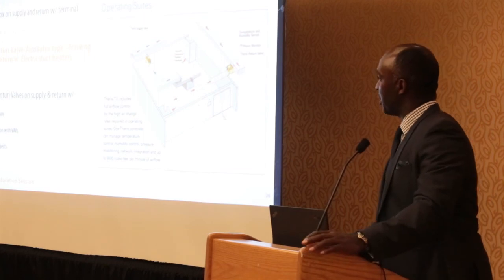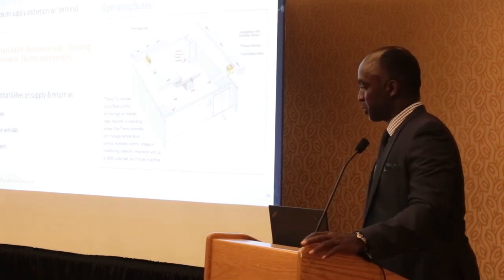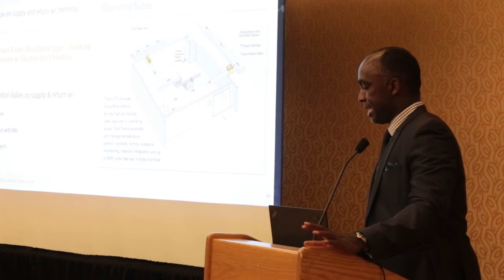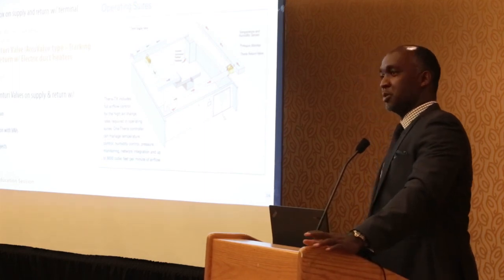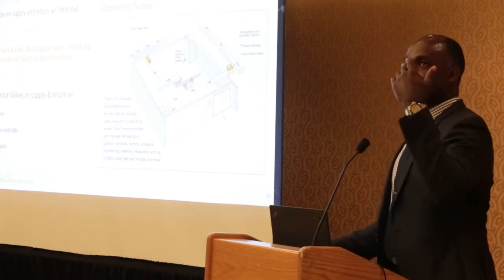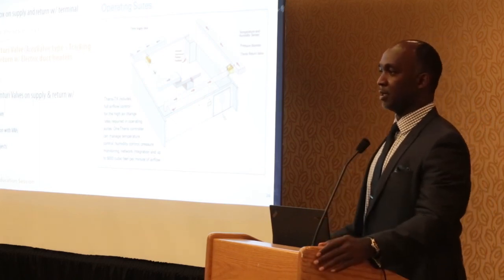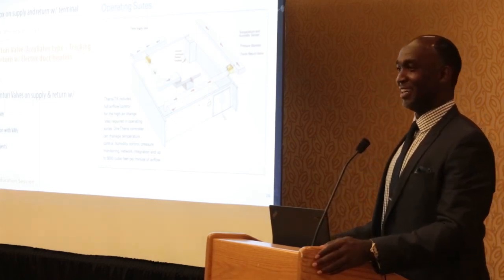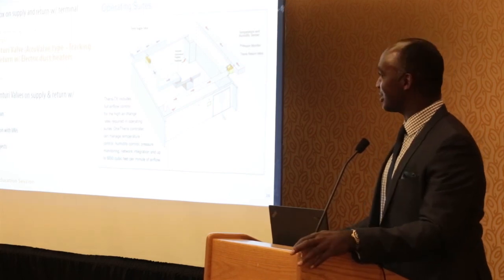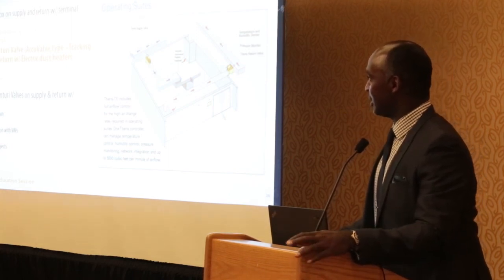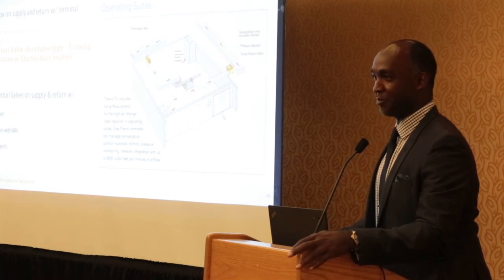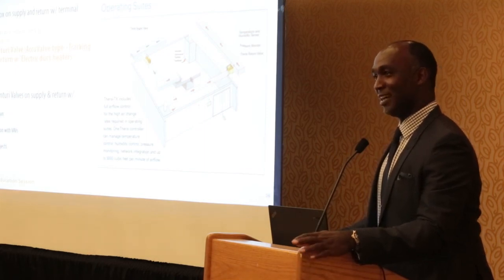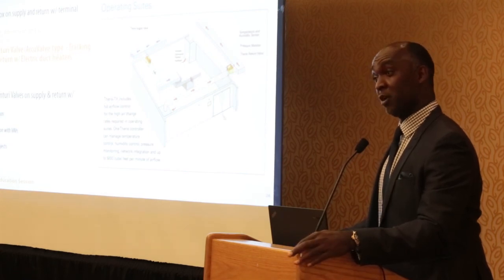Another important part of having pressurization deals with how the air is actually distributed in your ORs. So you have VAV boxes that serve a normal space. That's what's been used mostly. And the challenge with VAV boxes is that they have airflow sensors that go bad after a while. So if you don't have them checked on a regular basis, yearly, your pressurization is going to be off. And most ORs don't have a visual means of actually knowing that.